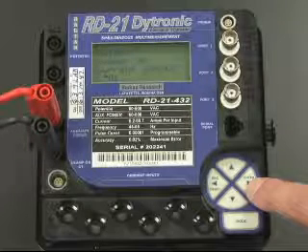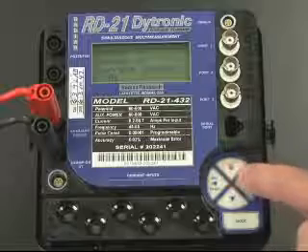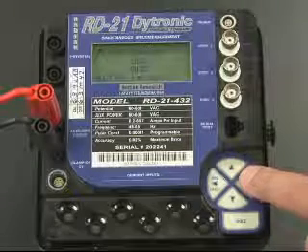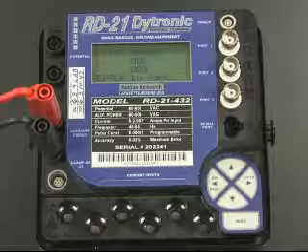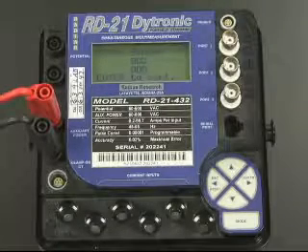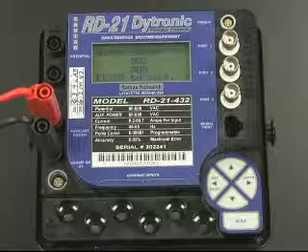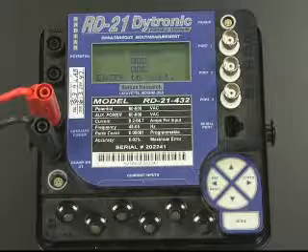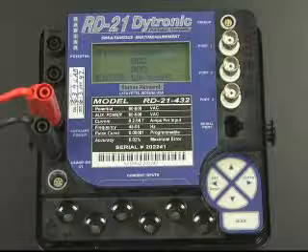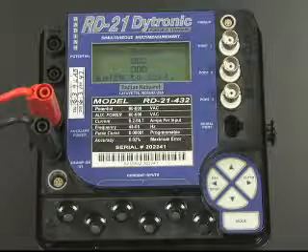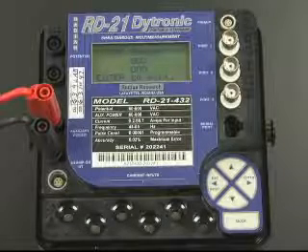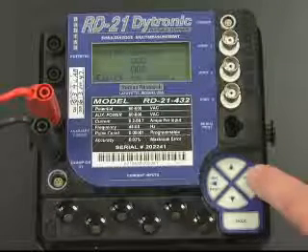From the phantom load, energize the meter with the correct current and voltage levels as detailed on the meter's faceplate label. Ensure that the grid on the Align sensor screen is pulsing each time an equivalent disk revolution occurs. Once correct sensor operation is verified, press the Enter button. Use the keypad to enter the desired number of test revolutions and press the Enter button. The standard will start the test when the next output pulse is sensed.